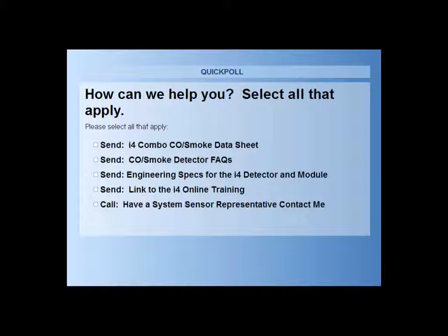Okay, so I'm looking at NFPA, and signals from carbon monoxide detectors. The integral sounder of a system-connected CO detector may be sufficient for notifying building occupants. Where CO signals are transmitted to a constantly attended on-site location or off-premises location in accordance with Chapter 7, selective mode occupant notification shall be permitted to be limited to the notification zone encompassing the area where the carbon monoxide signal originated. Okay, so that means you just need local annunciation, David.